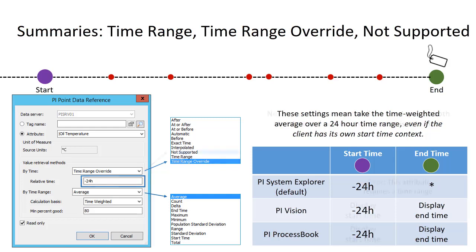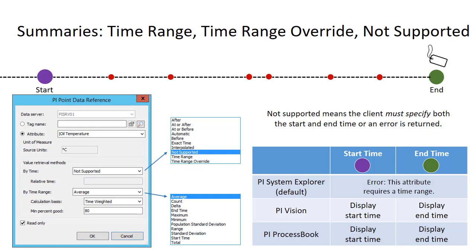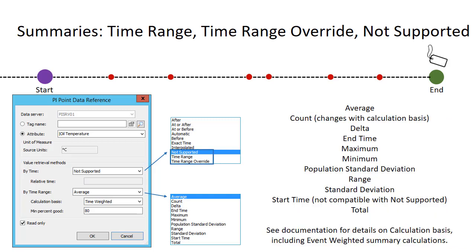The third summary call option is not supported. Not supported requires that both the start and end time are provided by the client. For PI Vision and PI ProcessBook, these will be the start and end times of the display. However, since PI System Explorer by default has only an end time context of now and no start time context, not supported will show an error in PSE. There are a large number of time range options available when using time range, time range override, and not supported. We used average, and the others are mostly self-explanatory, but details are provided in the documentation. If you wish to use a calculation basis other than time weighted, please see the documentation.